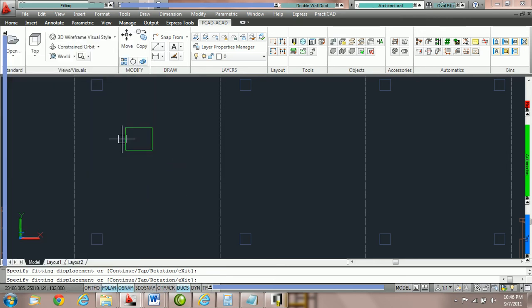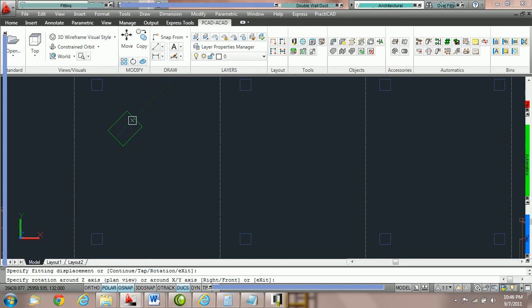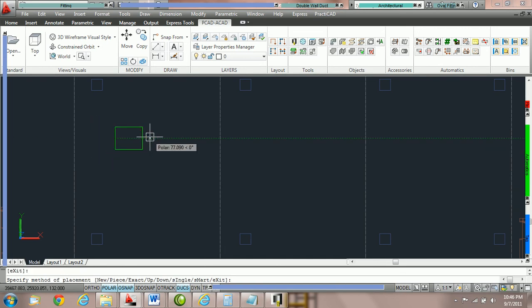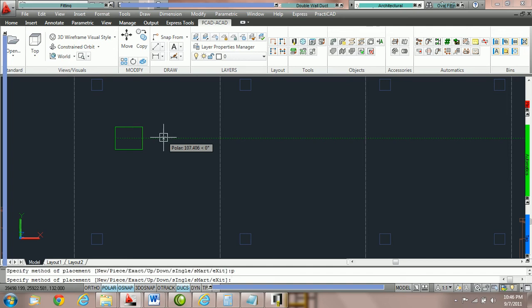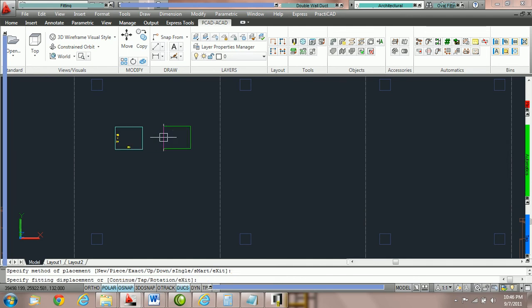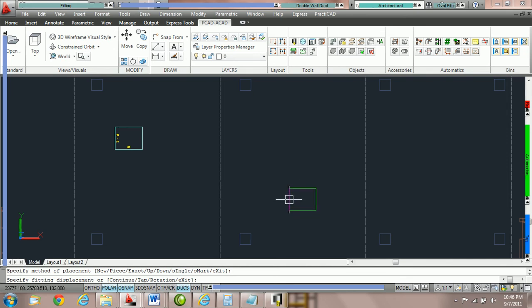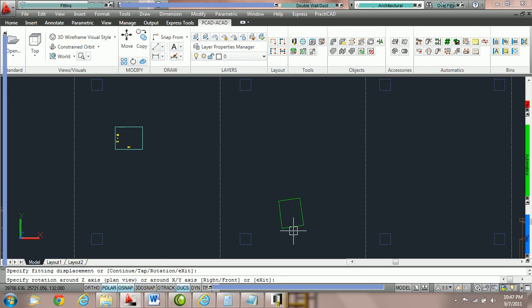Place this duct on your drawing left to right. We will click once, specifies the hold point, click twice for our rotation and now it's asking the method of placement in the command line. We're going to hit P for piece and spacebar to choose the piece routing method and click. Then come over to the next quadrant and place an identical fitting pointing in the downward direction.